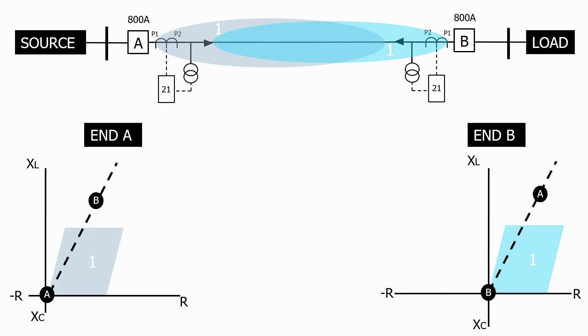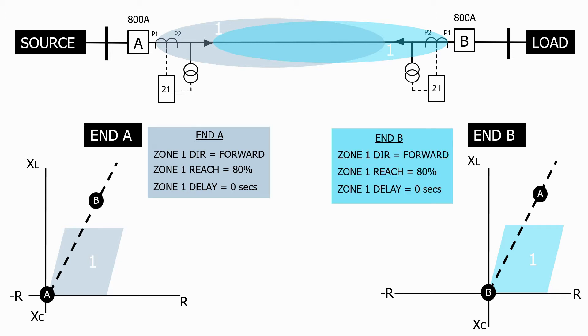Let's look at the characteristics. As usual the direction is forward looking down the line, the reach is 80% of the line length and the zone 1 delay is 0. We use the same characteristics for end B.